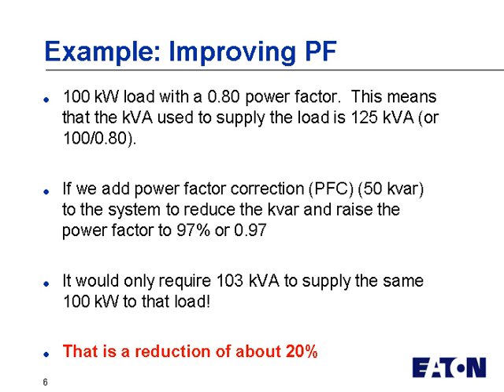We're going to give you a couple of examples here. First, as an example, we'll use a 100 kilowatt load with a 0.8 power factor, and this really means that the kVA used to supply the load is 125, or 100 divided by 0.8. If we wanted to correct the power factor from 0.8 to 0.97, we would apply, in this case, a 50 kVAR capacitor. And by doing that, we'd be able to reduce it from 125 kVA down to 103 kVA, just to supply that same 100 kW load.